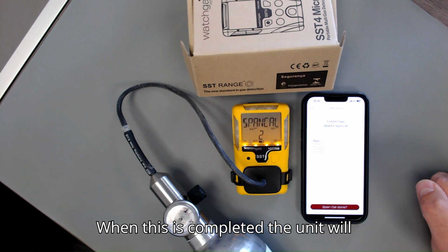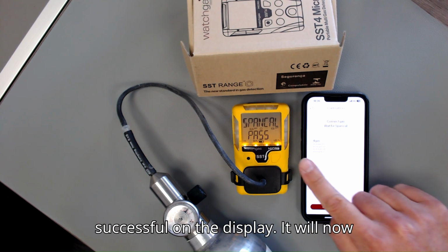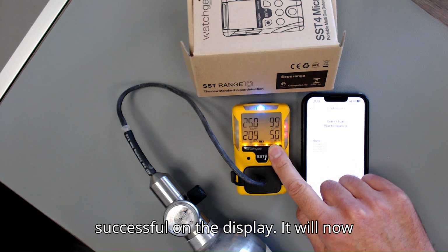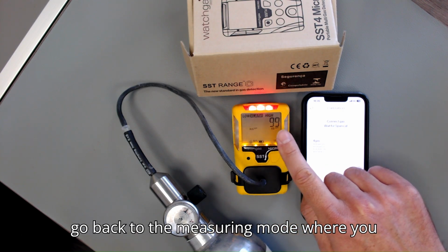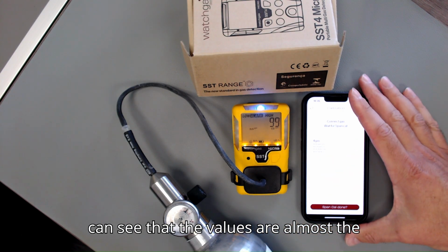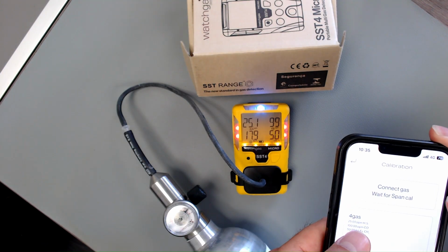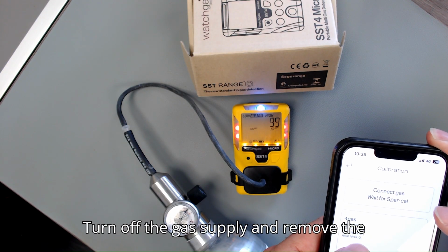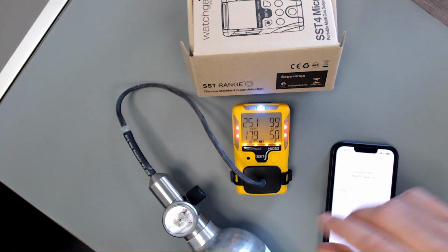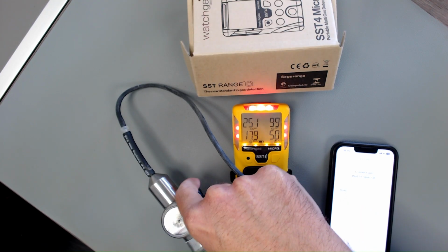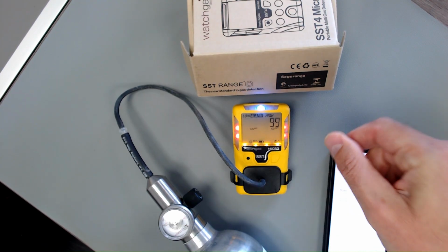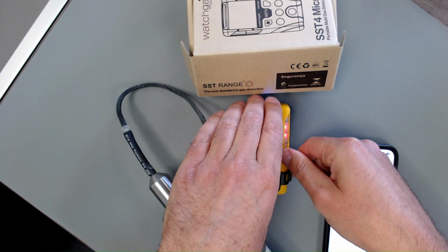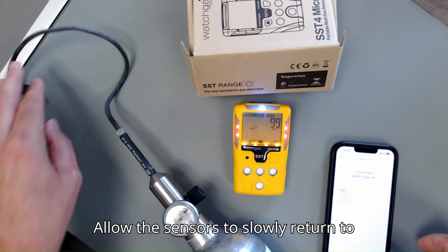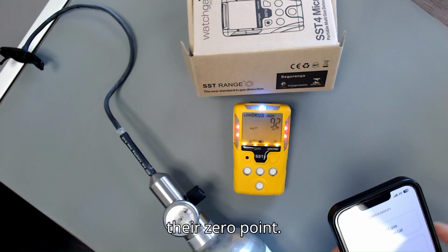When this is completed, the unit will indicate that the calibration is successful on the display. It will now go back to the measuring mode where you can see that the values are almost the same as the values in your gas bottle. Turn off the gas supply and remove the calibration cap. Allow the sensors to slowly return to their 0 point.